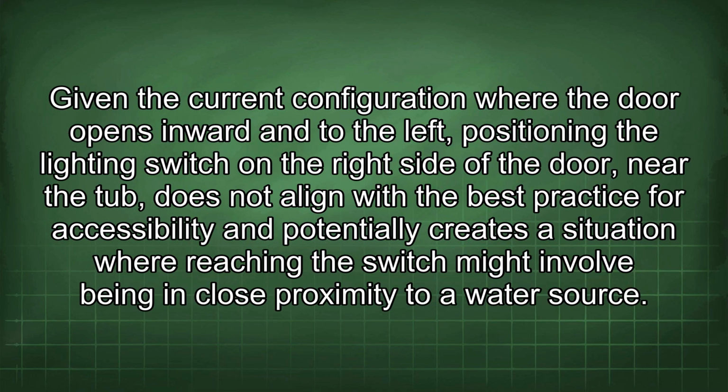Given the current configuration where the door opens inward and to the left, positioning the lighting switch on the right side of the door, near the tub, does not align with the best practice for accessibility and potentially creates a situation where reaching the switch might involve being in close proximity to a water source.